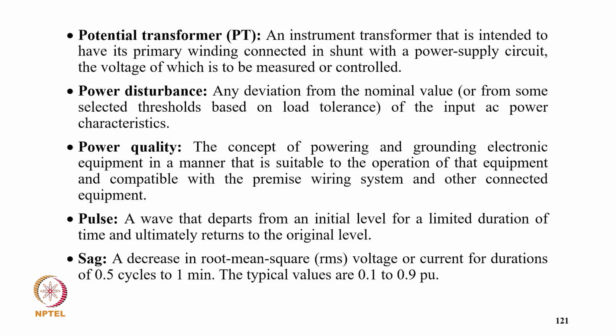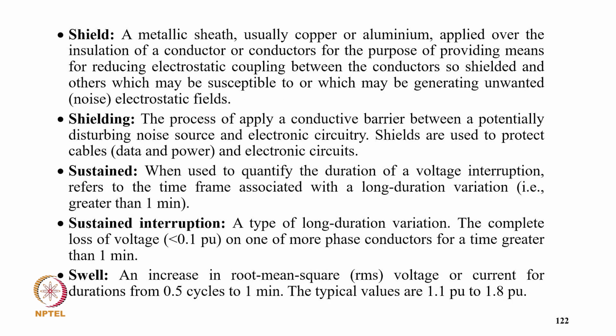Power disturbance: any deviation from the nominal value or from some selected threshold based on the load tolerance of the input AC power characteristic. Power quality: the concept of powering and grounding electronic equipment in a manner that is suitable to the operation of that equipment and compatible with the premise wiring system and other connected equipment. Pulse: a wave that departs from the initial level for a limited duration of time and ultimately returns to the original. Sag: a decrease in the root mean square voltage or current for a duration of 0.5 cycle to 1 minute. Typical values are 0.1 per unit to 0.9 per unit.